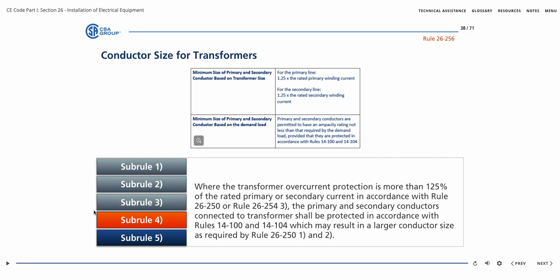Subrule 4 provides that where the transformer overcurrent protection is more than 125% of the rated primary or secondary current in accordance with Rule 26-250 or 26-254, Subrule 3, the primary and secondary conductors connected to the transformer shall be protected in accordance with Rules 14-100 and 14-104, which may result in a larger conductor size, as required by Rule 26-250, Subrules 1 and 2.